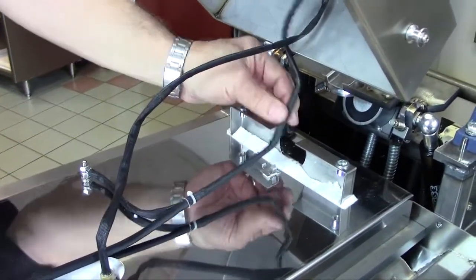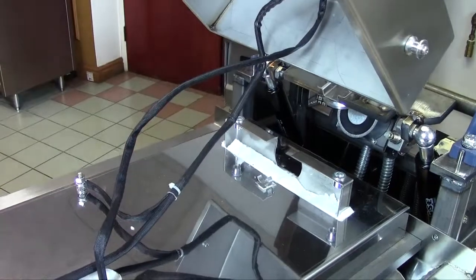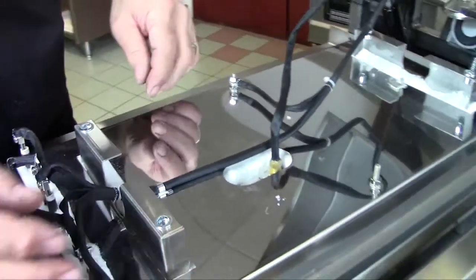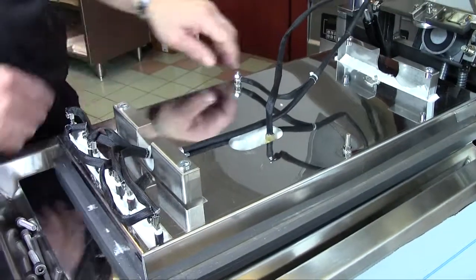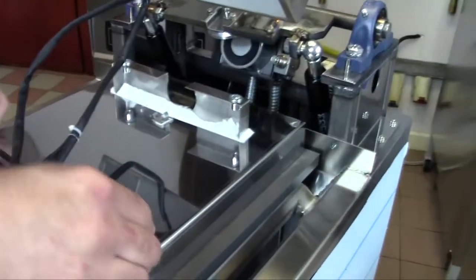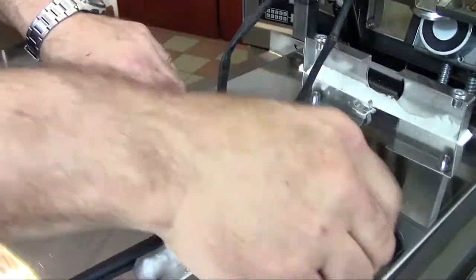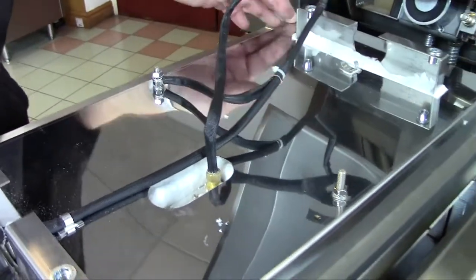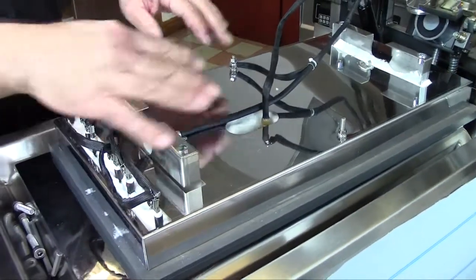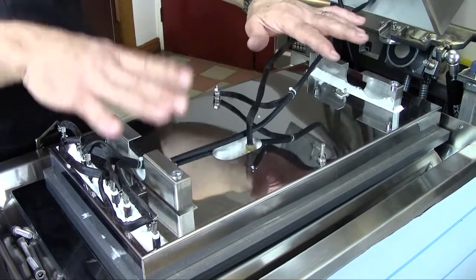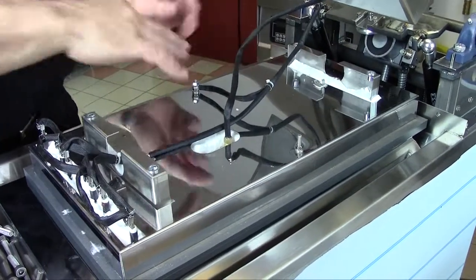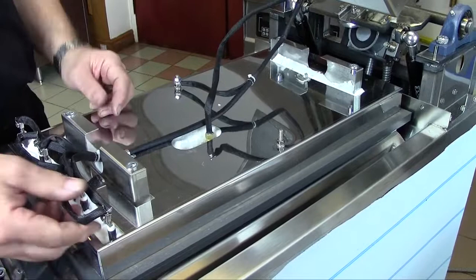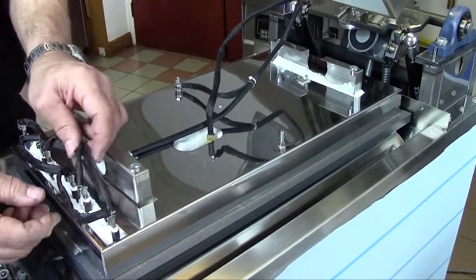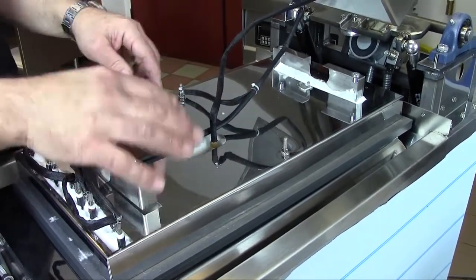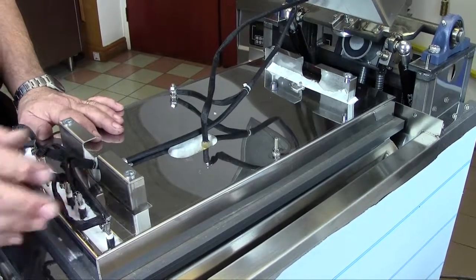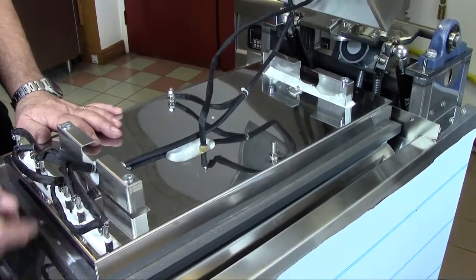Right, if you're replacing the elements, you remove these 2 bolts here, the wire on that one, and this plate comes up, and you have the same setup as on the bottom. You've got a plate with lots of bolts in which hold the elements in place, so it's exactly the same procedure. You just take all the bolts out, take the faulty element out and stick a new one in, no problem.